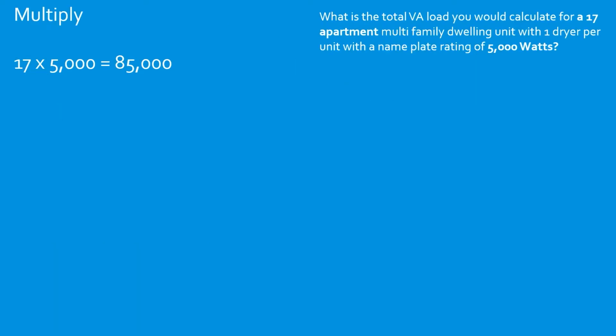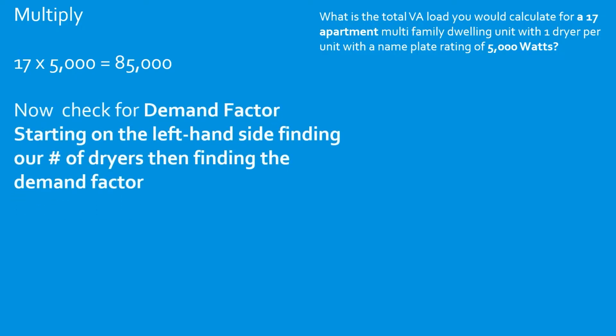First, we find out our total VAs. We take 17 multiplied by 5,000, and that's going to give us 85,000 VAs. That's the total that we're starting with. Then we're going to check for demand factors. We're going to head to table 220.54. We're going to start on the left-hand side of the table and find our number of dryers. Then we're going to come over and find our demand factor.